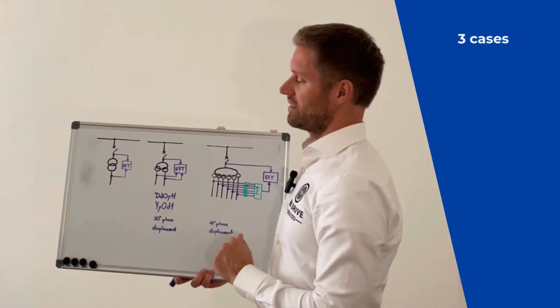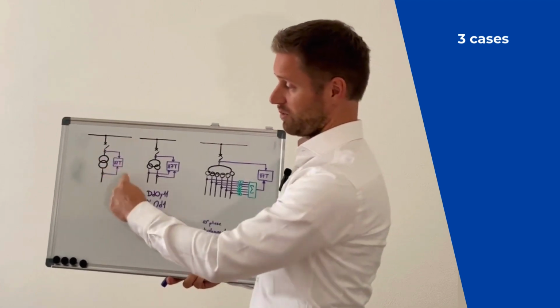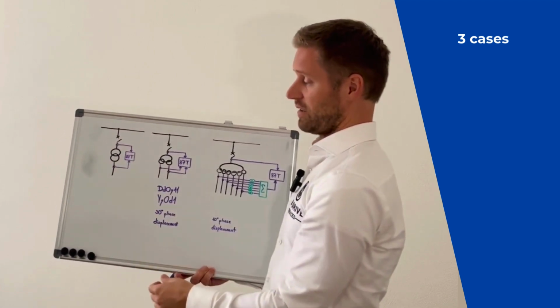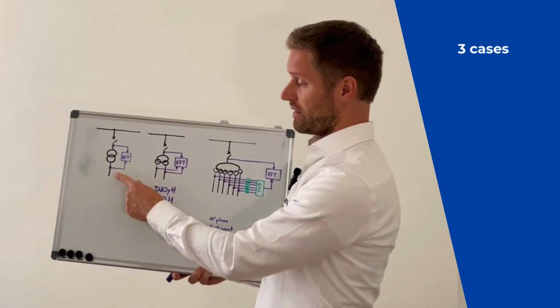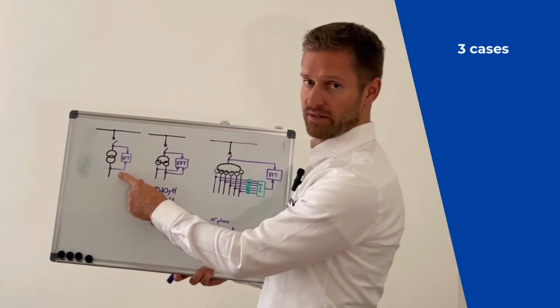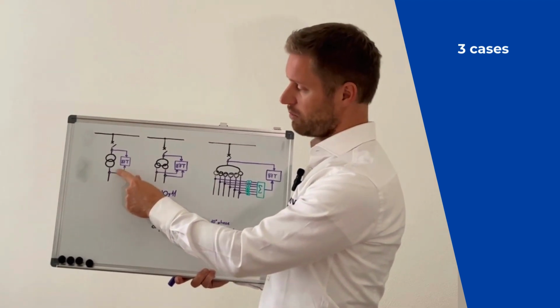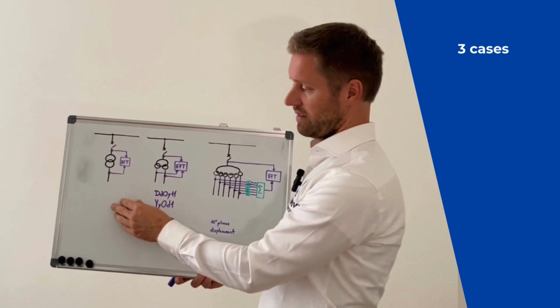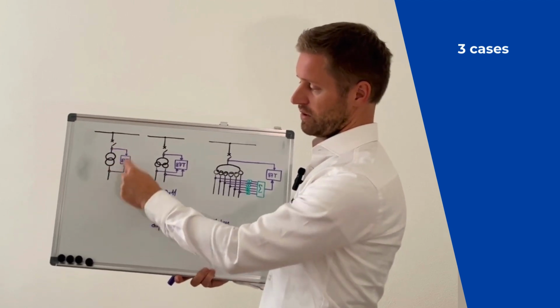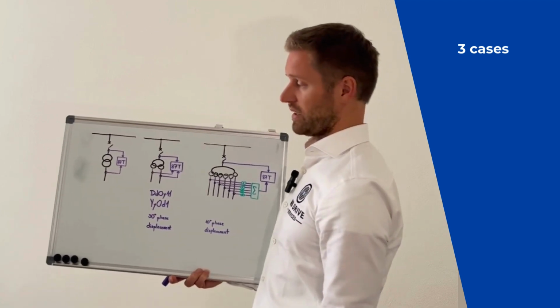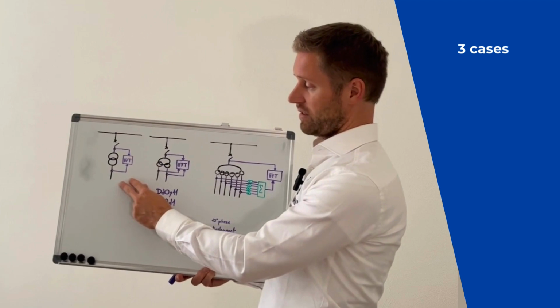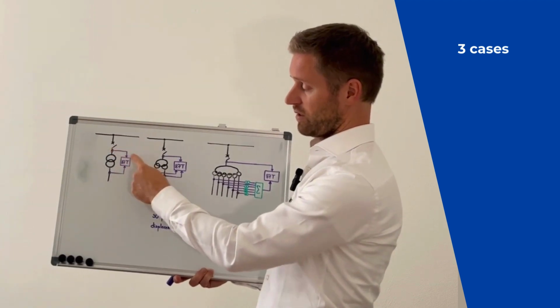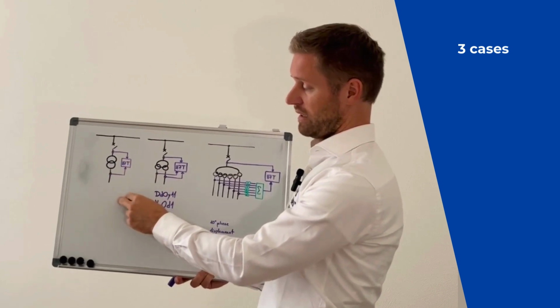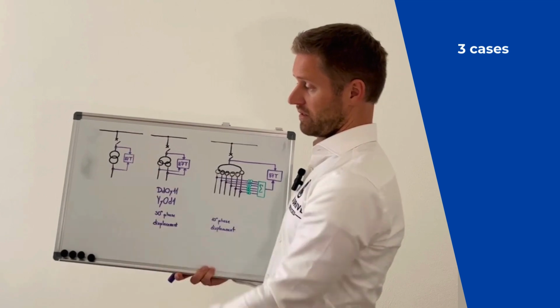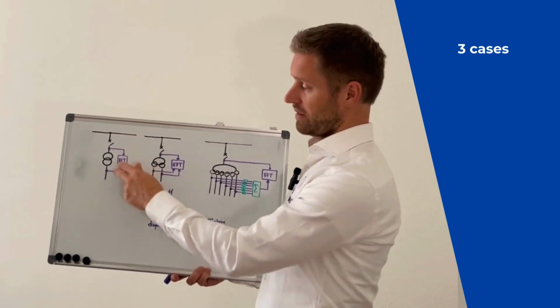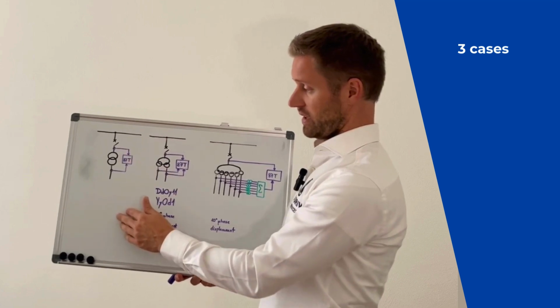We can see three cases here. The first one is the simplest possible transformer, just a two-winding like we have seen. This simple transformer can be used in VFD applications as well. It's not that common, but some active front-end type VFDs would just require this relatively simple two-winding transformer. So here the implementation is straightforward. We just measure current on the primary side, current on the secondary side, and we feed them into the differential protection relay that is then doing the job and comparing the currents.